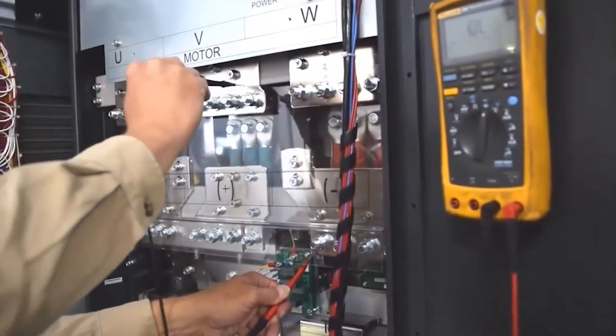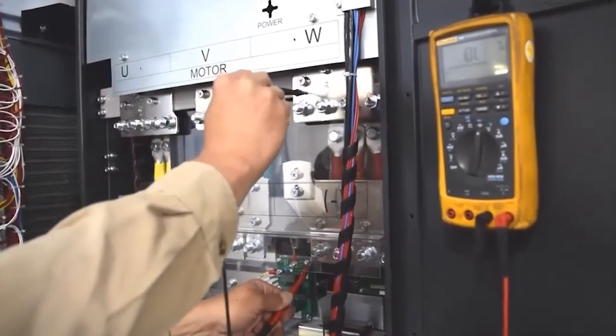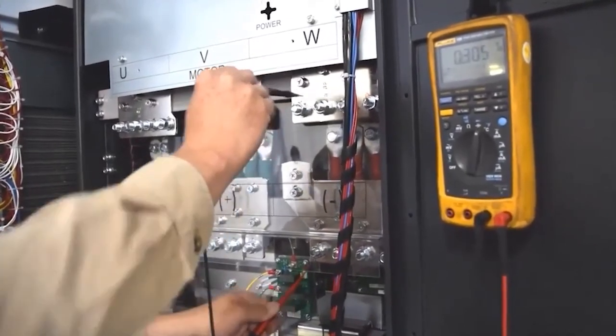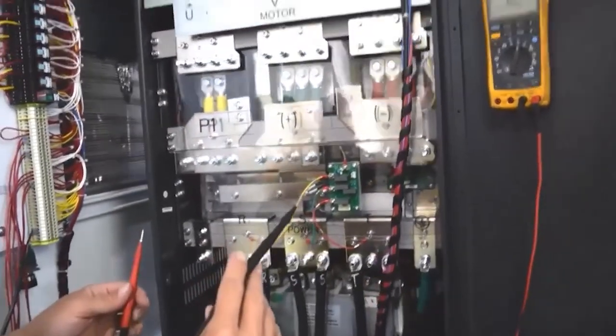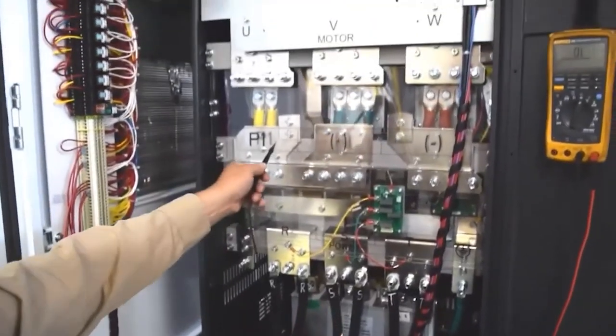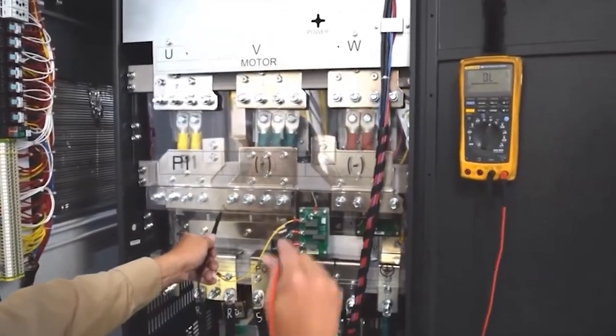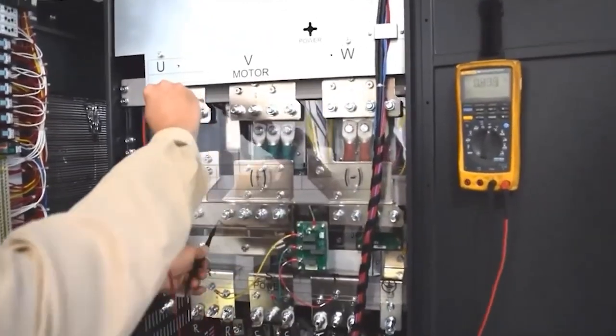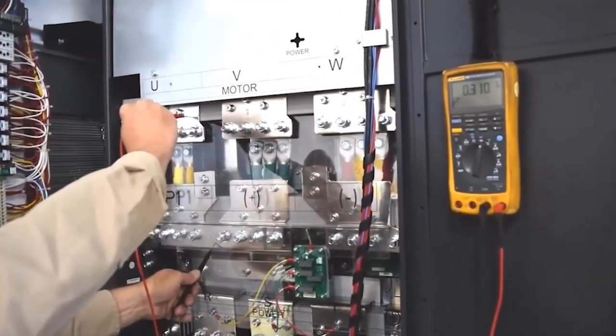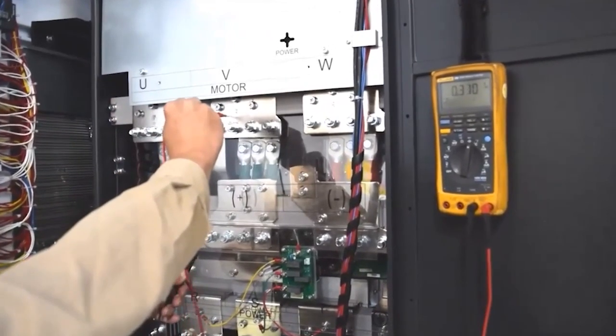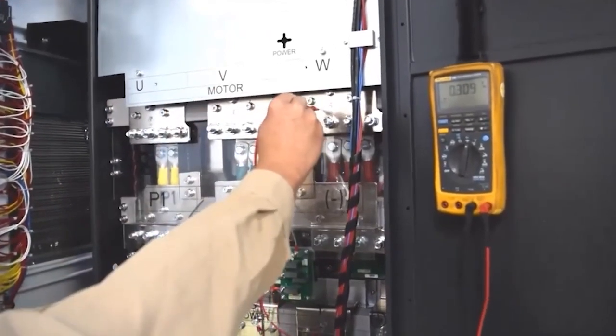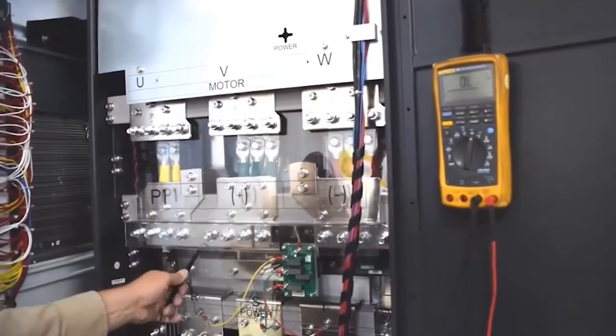I'm going to take my positive lead, put on my negative bus again. I'm going to measure all my T1, T2, T3, or my UVW phases. And I had 0.305 all the way across on that one. I'm going to take my negative lead, put on my positive bus, and do the same measurement. And 0.310, 0.310, and 0.310 all the way across here.